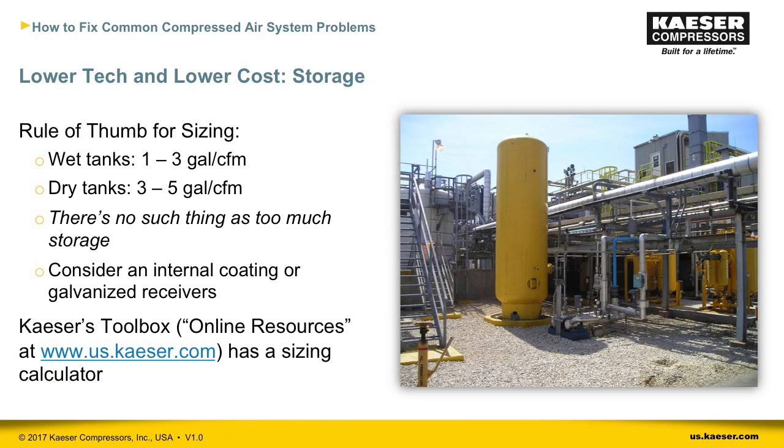Also consider galvanized receivers, or internally coated receivers, as these will protect the receiver from rusting over time. When you consider that some receivers are installed for generations, we recently saw one from 1949, this can cause the internals of the tank to rust and scale due to the acidity of compressed air condensate, which then gets passed downstream to the end use. Whereas an internally coated tank or galvanized receiver can last much longer.